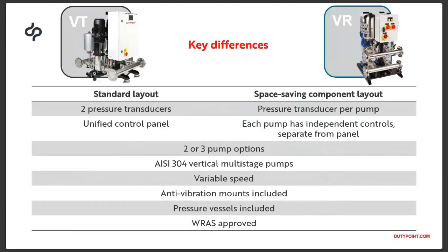The VR has motor-mounted inverter drives, which are usually the Xylem Hydrovar units. So it's also available with Vascos, whereas with the VT, all the inverter drives are actually contained within the control panel. So you can actually see on the image, the pump doesn't have any inverter drives on the top. It's still a variable speed set. It's just the inverters are actually within the control panel. Which is quite nice from a maintenance point of view, because all the controls, all the electronics are really contained within that one control panel. And those really are the key differences.